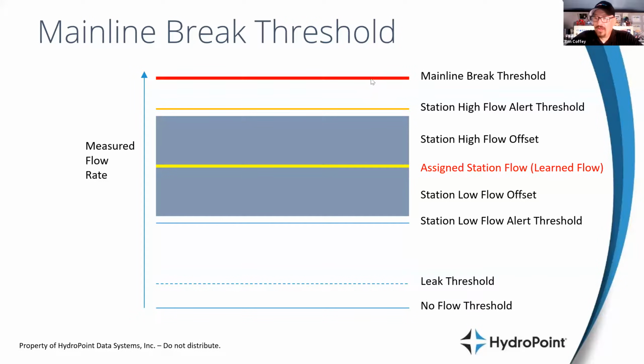It gets a little trickier when you are running more than one station at a time, because we have to anticipate that. We have to calculate the highest anticipated flow. So if you have two stations running at once and they're both at 100 gallons a minute, you can't set your mainline break to 120 gallons a minute, because normal irrigation would push you to 200 gallons a minute. So again, if you've got two running at the same time at 100 gallons a minute, we add those together to give us our highest anticipated flow, and then set your mainline break threshold to 20% above that.